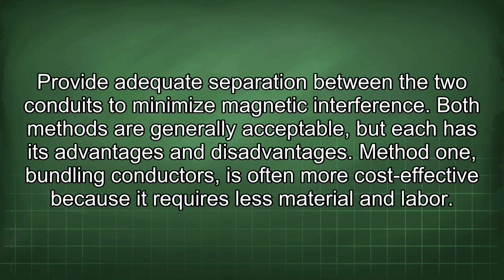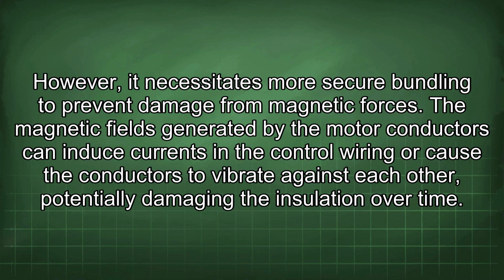Both methods are generally acceptable, but each has its advantages and disadvantages. Method 1, bundling conductors, is often more cost-effective because it requires less material and labor. However, it necessitates more secure bundling to prevent damage from magnetic forces. The magnetic fields generated by the motor conductors can induce currents in the control wiring or cause the conductors to vibrate against each other, potentially damaging the insulation over time.